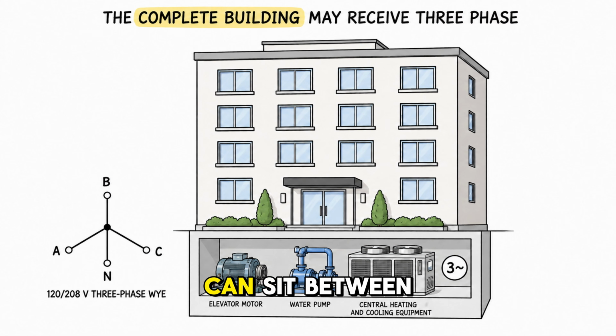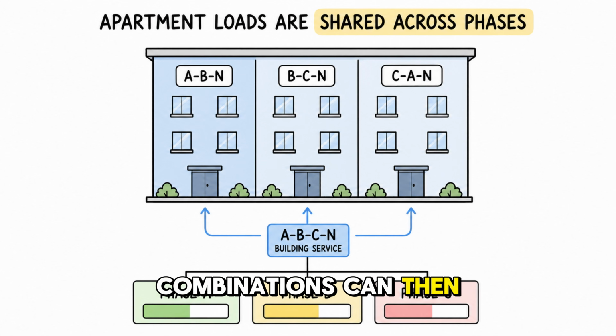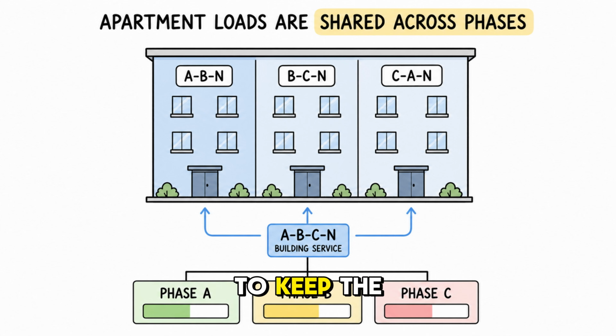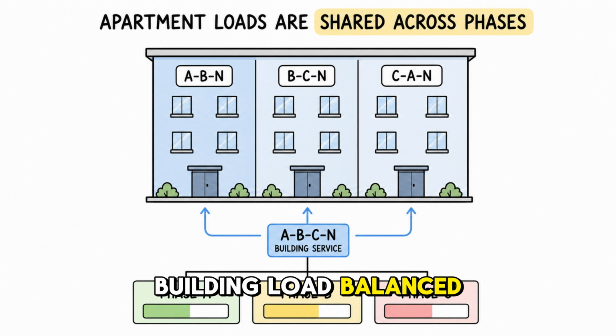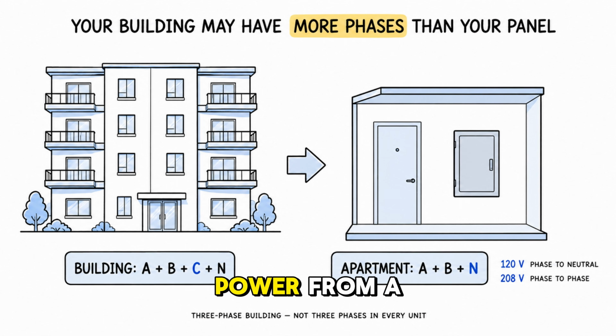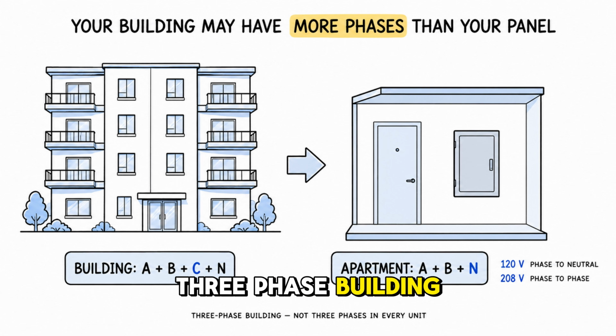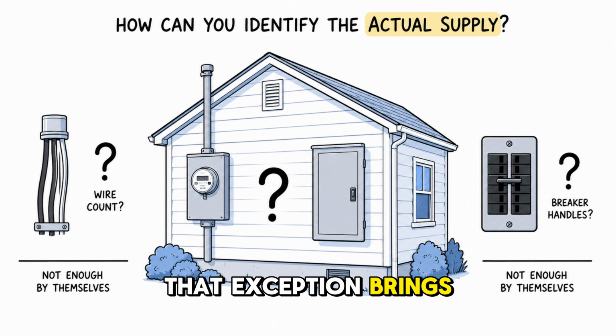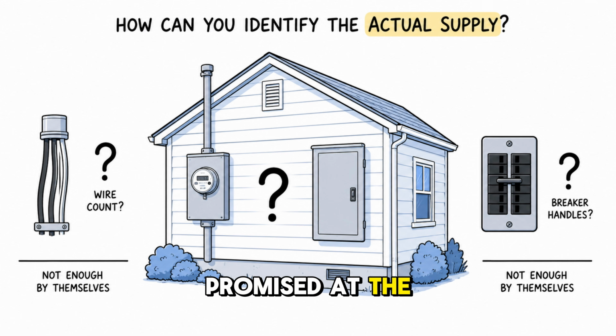Large apartment buildings can sit between these two situations. The complete building may receive a 120 and 208 volt three-phase Y service because elevators, pumps, and shared mechanical systems benefit from it. Different phase combinations can then be distributed among the apartments to keep the total building load balanced. This means your apartment can receive power from a three-phase building, even if all three phases do not enter your apartment panel. That exception brings us back to the question promised at the beginning.